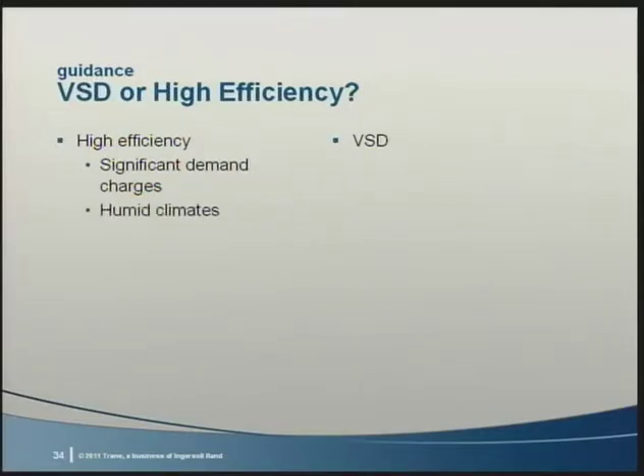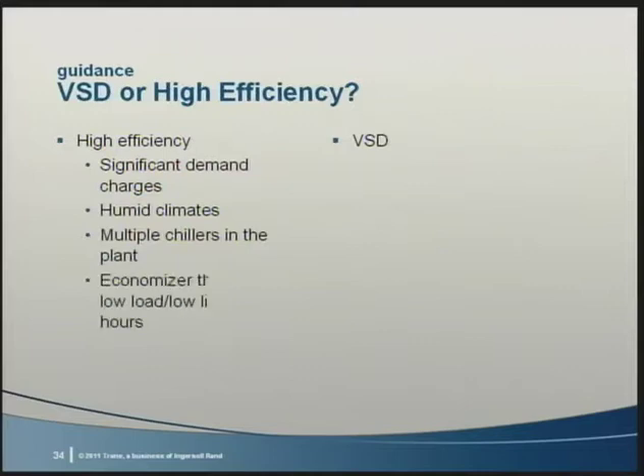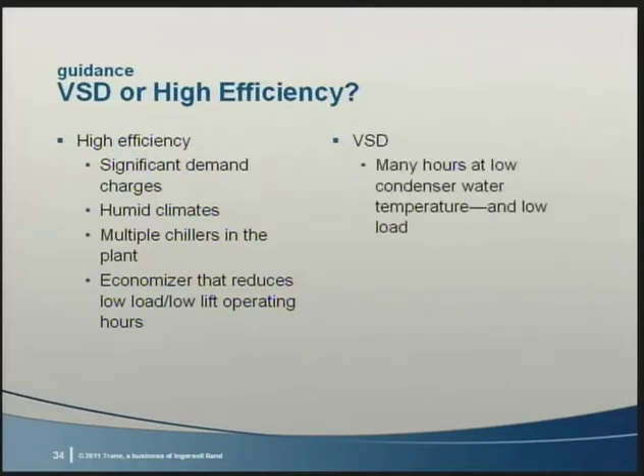In addition, if there are multiple chillers in the plant, the new chiller may never operate at less than 50% load, and it may operate at high load conditions quite often. If there is an air side economizer on the building, the chiller may be off during hours that a VSD would benefit. If there are many hours at low condenser water temperatures, consider a drive, but perhaps the best economics are to only put it on one chiller.